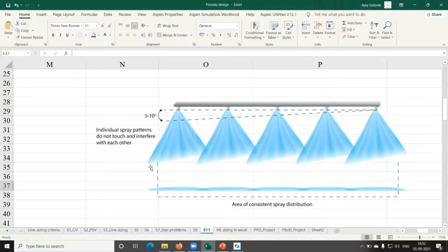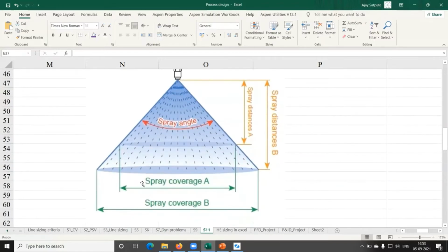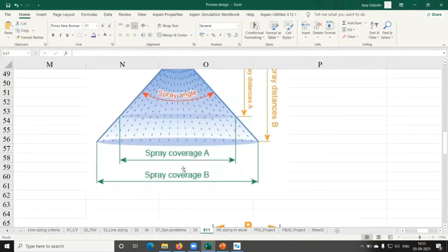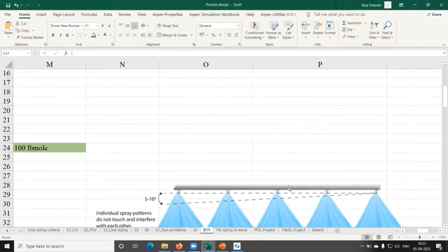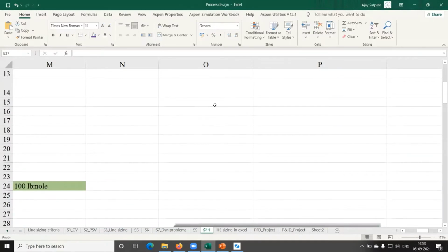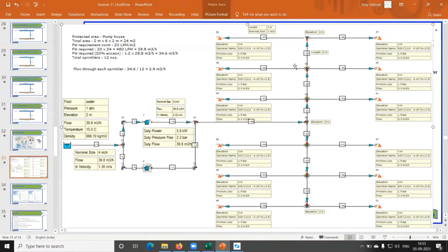So the vendor will tell that if you give a minimum of, say, 1.5 bar gauge pressure at the inlet, then I can assure that the spray coverage area would be, let's say, 3 meters or 4 meters, whatever, right? So taking that information from the vendor, piping will create a diagram, the top view, and it is our job to approve that, right? So once that gets approved, then we'll prepare our model.